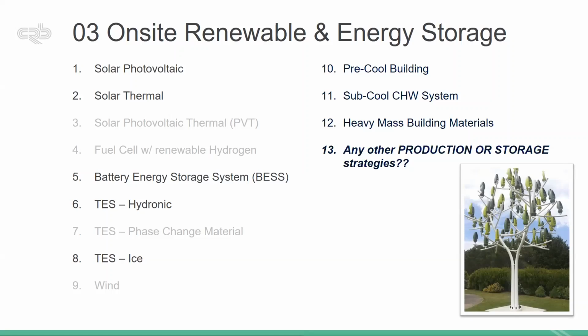One of the simple ones I really like is number 10 and 11 on this list. We're getting hit with these 4 to 9 p.m. time of use peak pricing from SDG&E. Why not turn down the temperature of the building across the board a degree or two, starting at 3 o'clock? And instead of running your chilled water plant at 42, 44 degrees, why not subcool it, drive it down to 38 degrees? It's interesting that when I got into the industry, we always talked about running our chillers at night when it was most efficient. But now we're talking about running them during the day, because that's when we have this influx of photovoltaics on the grid. We actually want to run more power during the middle of the day.